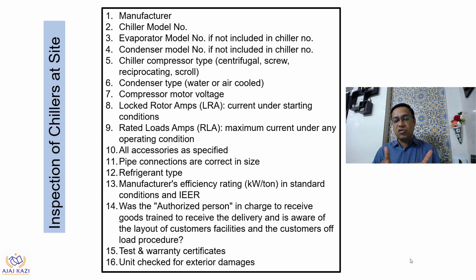Then all accessories. Remember, there are a lot of accessories which the chiller manufacturer may supply or which may be part of the scope, like vibration isolators, or the Victaulic coupling at the flange or the tapping of the chiller or condenser. Some of these may be part of the scope, and whether they are delivered or not needs to be checked. Then the pipe connections of the chiller and condenser: are they of correct size, or is there a mismatch? Because you have done the piping based on that and then you find a mismatch. Also check the refrigerant used in the chiller being delivered, whether it is as per the approved submittal or not.